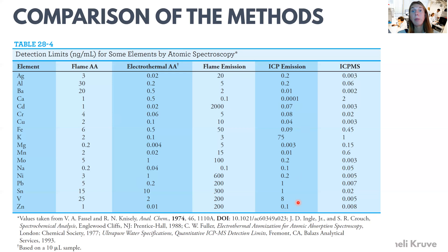However, the problem with ICP emission spectroscopy is extremely high investment costs, as well as very, very high maintenance cost of the instrumentation. So this technique is applied when we need very low detection limits. But the requirement here for this instrumentation to actually pay off is to have very many samples on a daily basis to be analyzed. So for real laboratories that main focus is on elemental analysis, atomic emission spectroscopy with ICP is a good choice. And similarly low or even sometimes even lower detection limits can also be achieved with ICP-MS. However, similar drawbacks as to ICP atomic emission spectroscopy apply here.